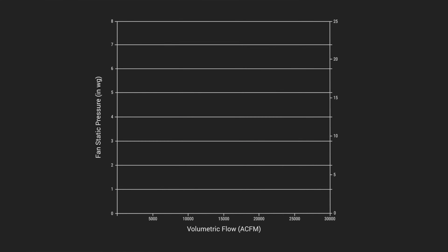This resistance, quantified as static pressure, is plotted on the system resistance curve, showing its resistance to each quantity of airflow. So when you ask for a fan that can produce 20,000 CFM at 5 inches of static pressure, that means you're planning to install a fan in a system that will resist the fan's 20,000 CFM with 5 inches of static pressure.